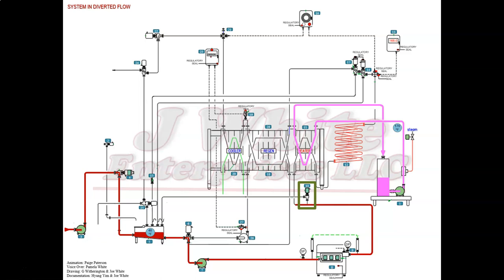The pressure relief valve protects the plate heat exchanger from the high pressure of the timing pump if a valve is closed downstream, the cooler section freezes up, or there is too much burn-on in the heater section.